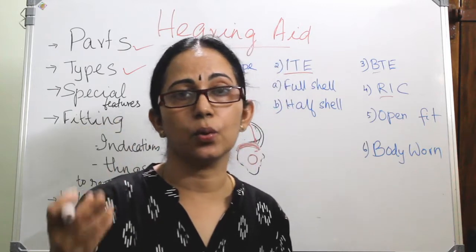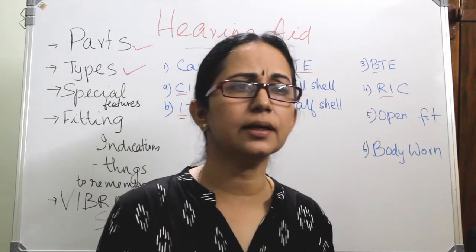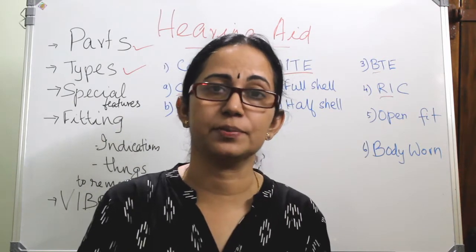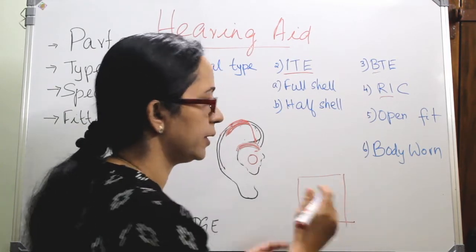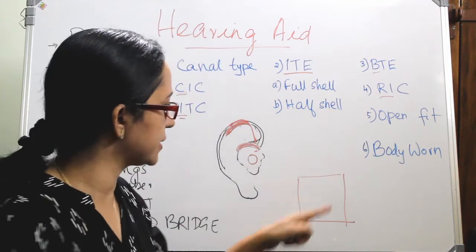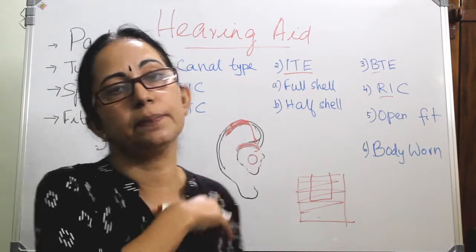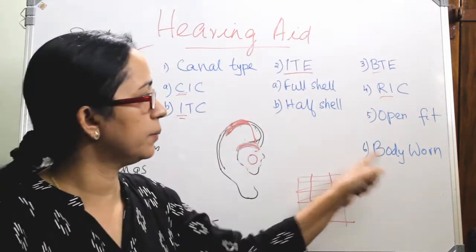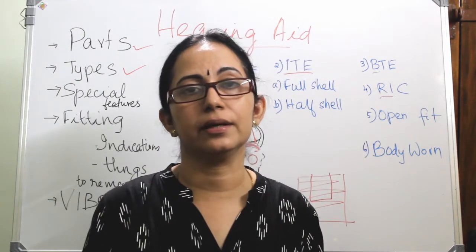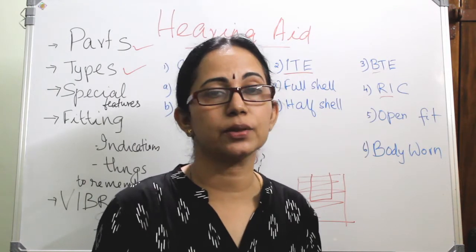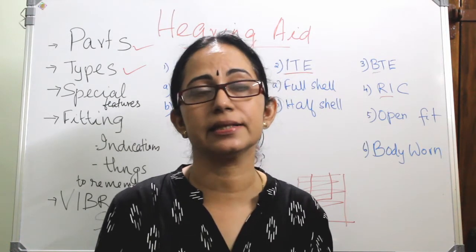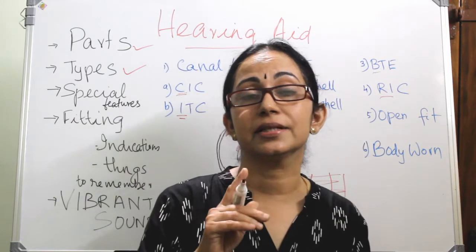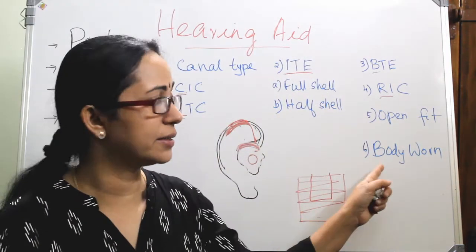Body worn is an older, possibly the earliest, type of hearing aid. The entire system — microphone, amplifier, receiver, and battery — is kept in one unit clipped into the pocket, with an ear insert connected via a wire. It costs around 1,500 to 2,000 Indian rupees, manipulation is easy, and battery life is long. Rechargeable batteries are now available for body worn aids. The main disadvantage is that cosmetically it is not appealing at all.